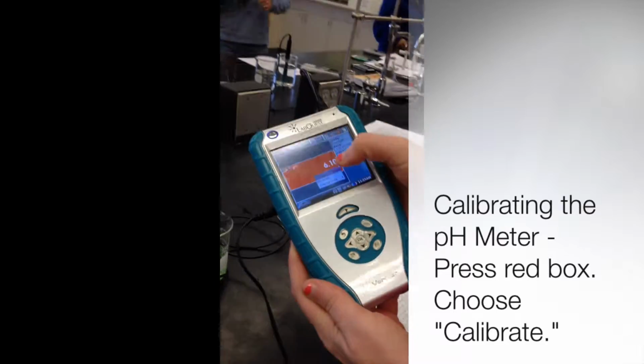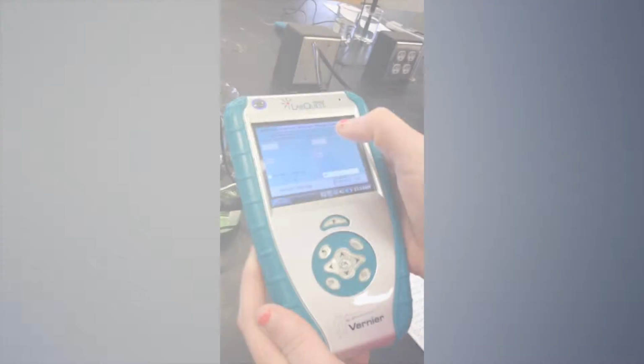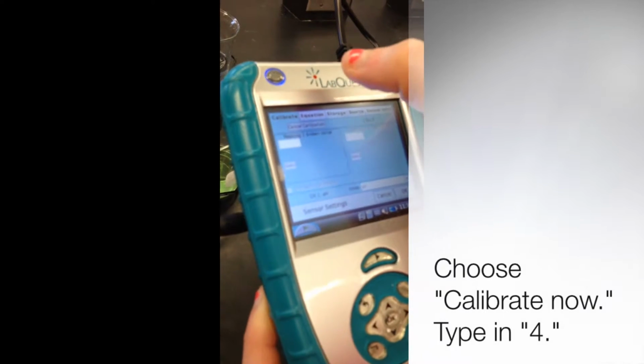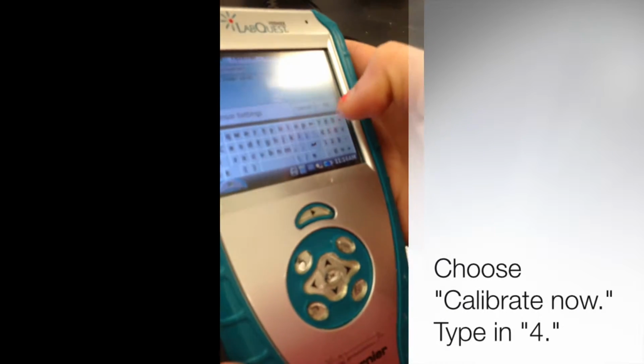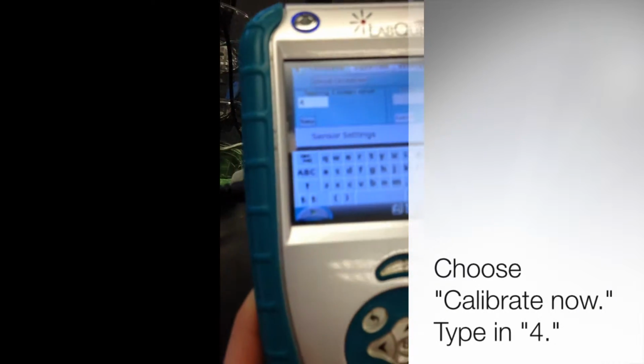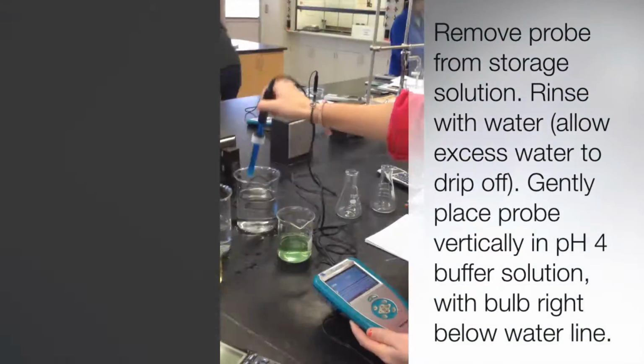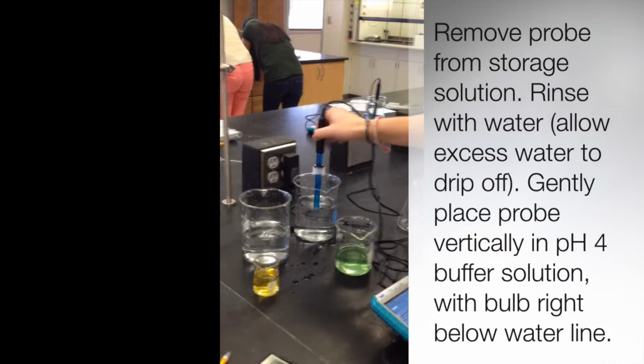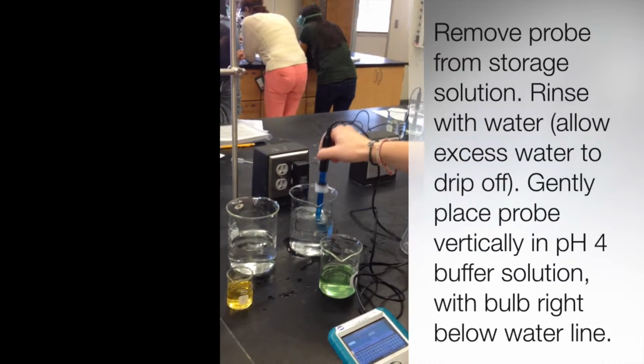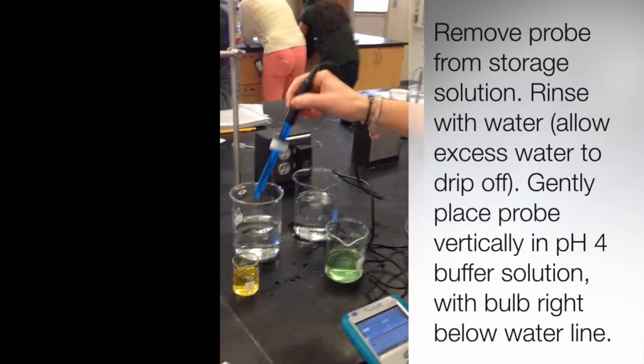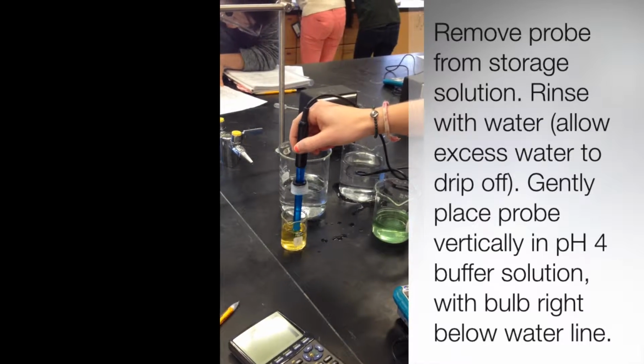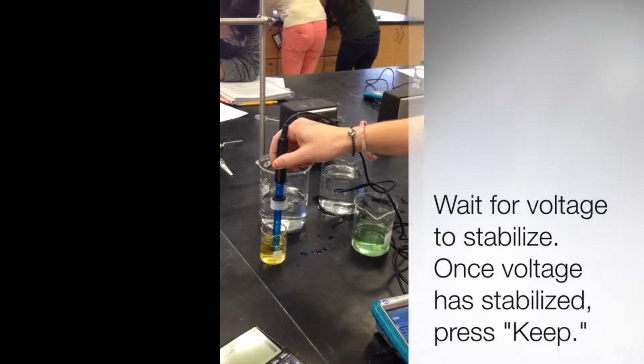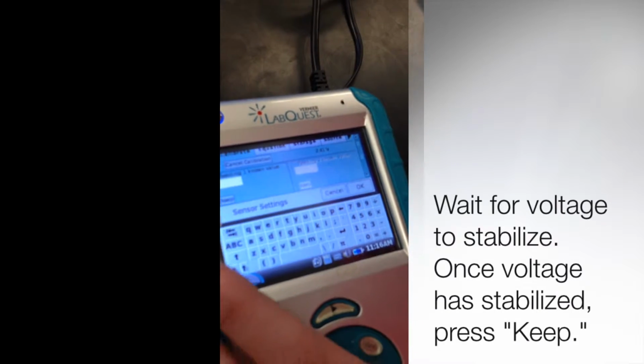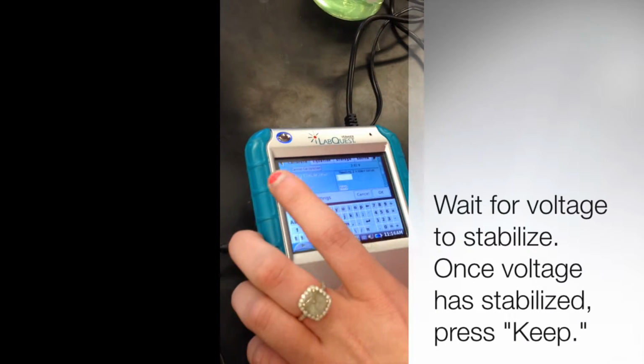Box in the middle, click calibrate, then I'm going to hit calibrate now, and I'm going to go ahead and hit 4 because we're calibrating with the pH 4 buffer. So I'm going to take the probe, taking it out of the storage solution, and I'm rinsing it in H2O. And now I'm going to place it in the pH 4 buffer right below the water line, keeping the probe vertical, and we're waiting for the voltage to stabilize. It looks like it's stabilized at around 2.41, and I'm going to press keep.